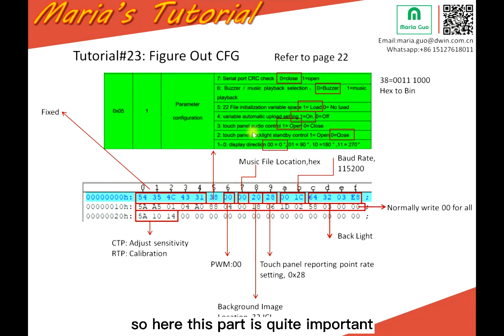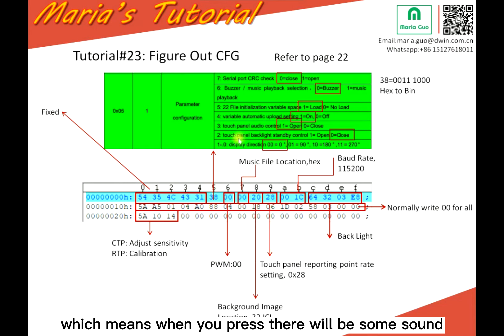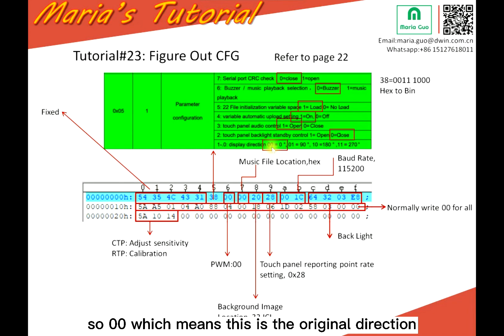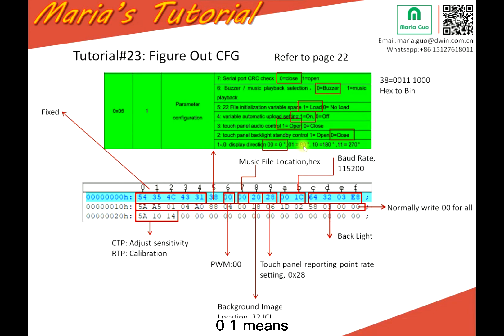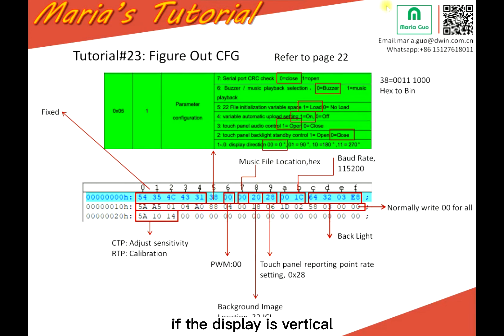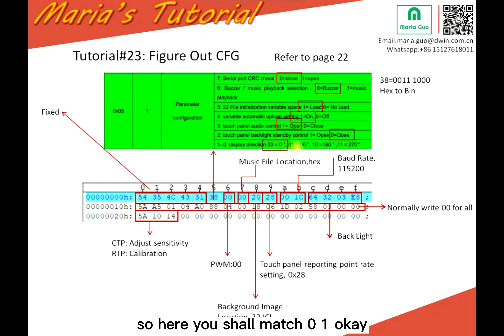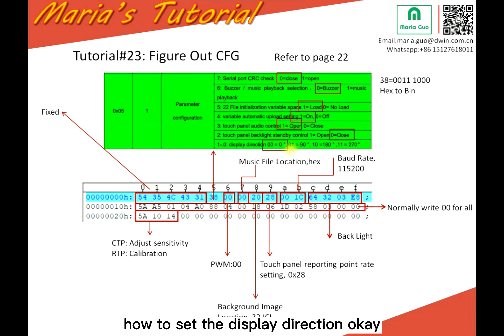This part is quite important. And here, this is the touch panel audio control — one means open, which means when you press, there will be some sound. And this is the backlight — open or zero. And this is the display direction. So 00 means the original direction, and 01 means changed angle. So if the display is vertical in factory settings, and you want to show the project in horizontal format, you should match 01. This is how to set the display direction.